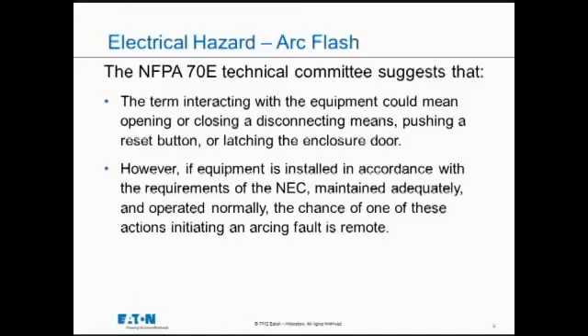What happened after 2008 was, in the United States, the companion group, the National Fire Protection Association, and their 70E, which is equivalent to the Canadian Z462. They made this suggestion that if you do operate a circuit breaker, open or close it, and the equipment is properly installed, in this case according to the National Electric Code, which would be the companion Canadian code in this country, you've maintained it adequately, that's a very large wild card, and you operate it normally, you're not doing something unusual, then the chance of an arc flash occurring, opening or closing a circuit breaker, is remote. They would never say it's non-existent or there's zero chance. They'll just say it's a pretty low chance. So that has come out recently.